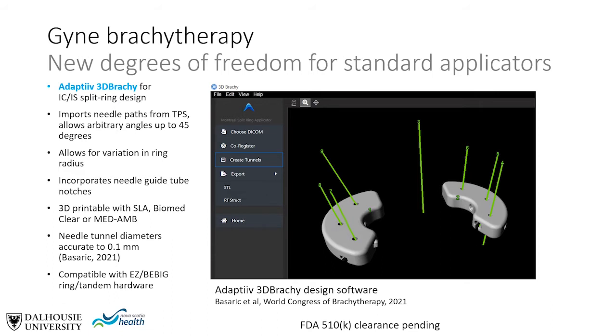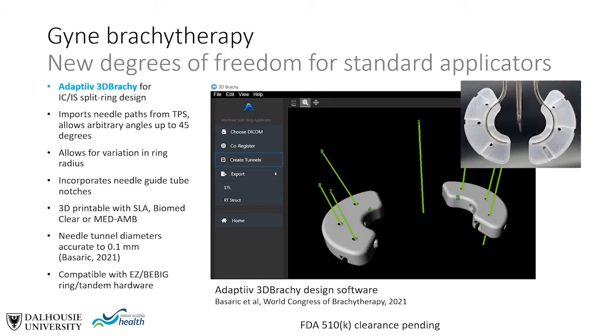Here's another example of extending the design of a standard applicator, in this case using the Adaptiiv 3DBrachy software for design of an intracavitary-interstitial split ring. This application imports needle paths from the TPS, allowing arbitrary angles of up to 45 degrees as well as definition of the ring radius. The design also incorporates needle guide tube notches to ensure stability. In the work by Basaric et al. presented this year at the World Congress of Brachytherapy, SLA methods using BiomedClear or MedAMB resins were used, with accuracy on the order of 0.1 millimeters.